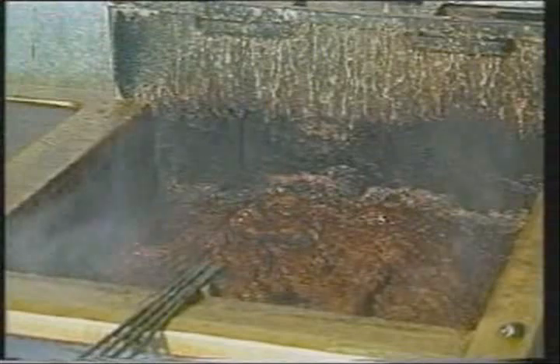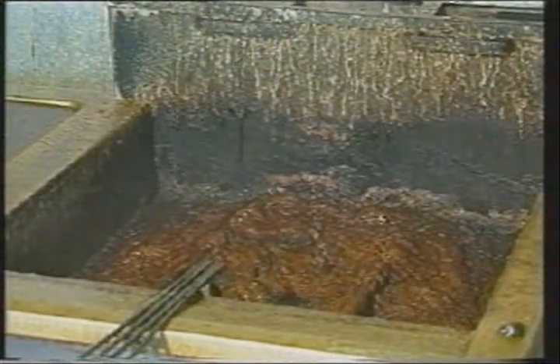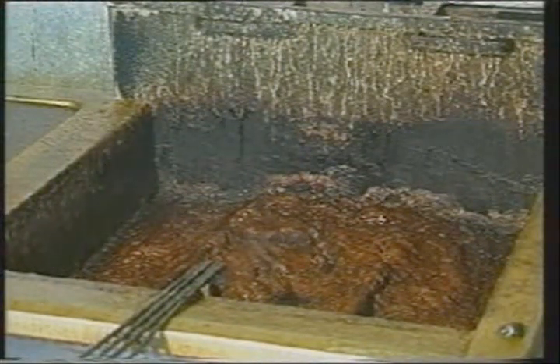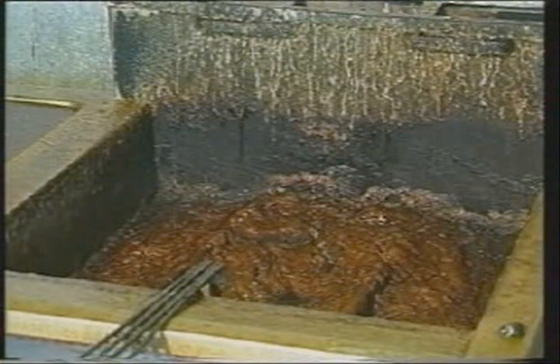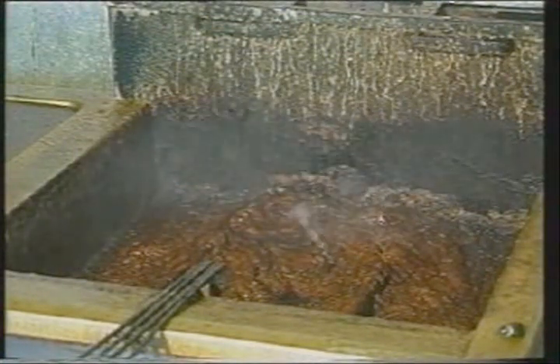The fire was totally suppressed during the R102's 34-second discharge. Along with immediate suppression of the fire, the Ansulex agent formed a stabilized layer on the surface of the oil by the action of saponification. This protective layer prevented any reflashing of the fire.